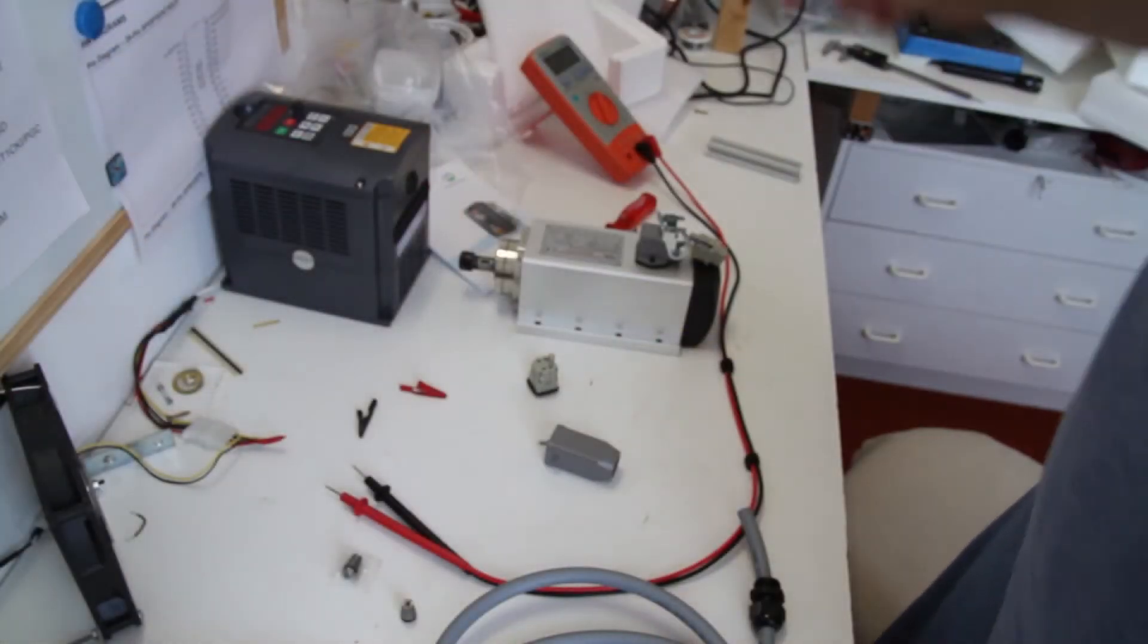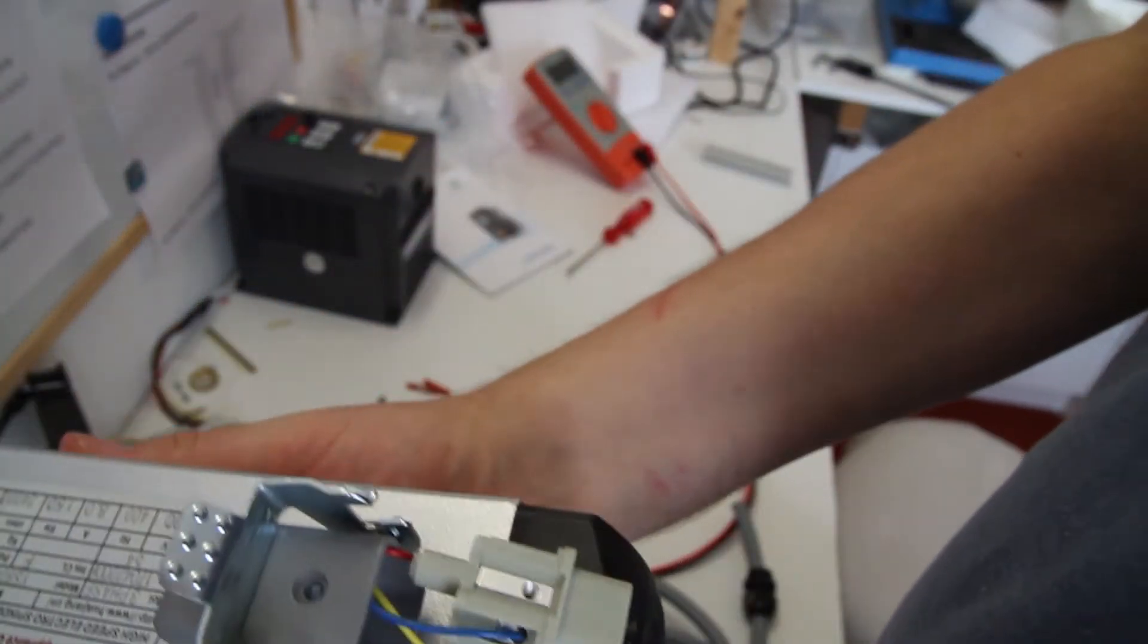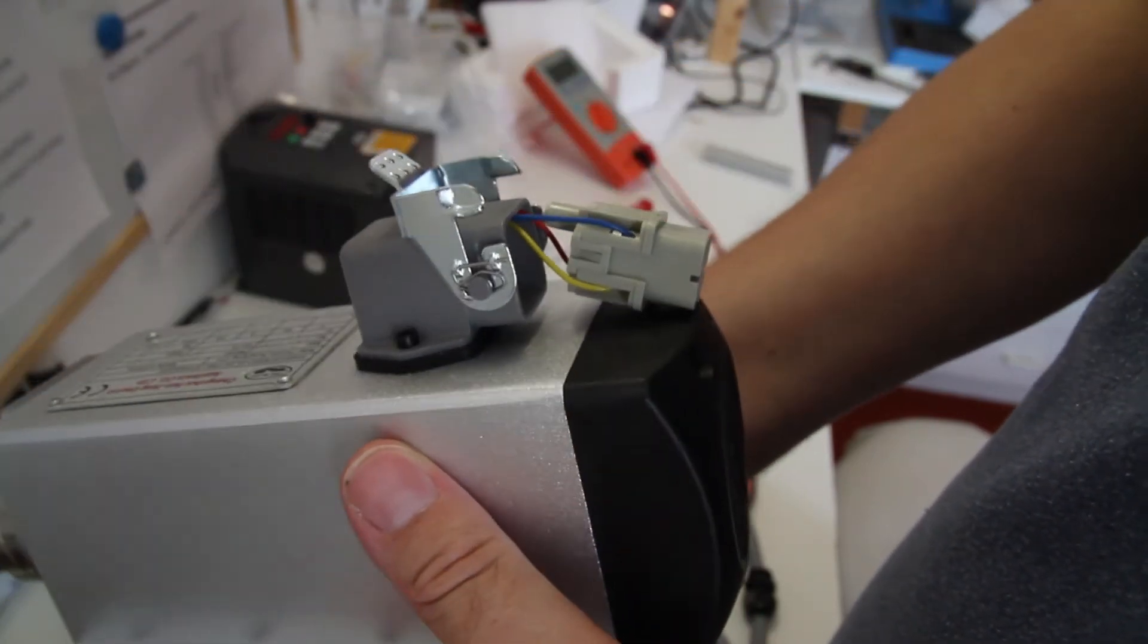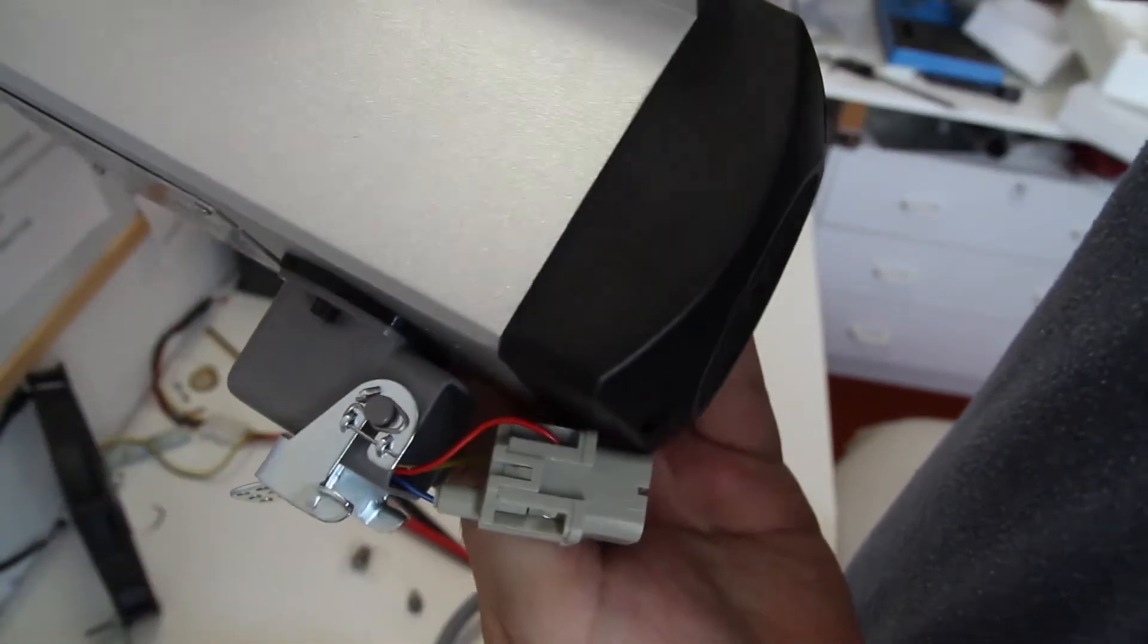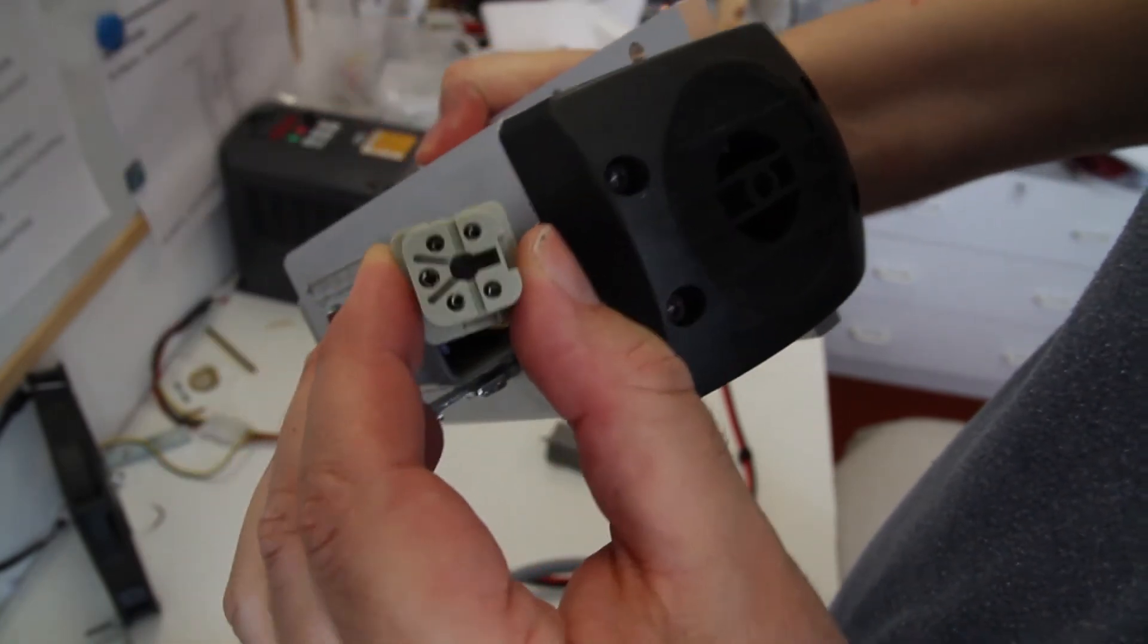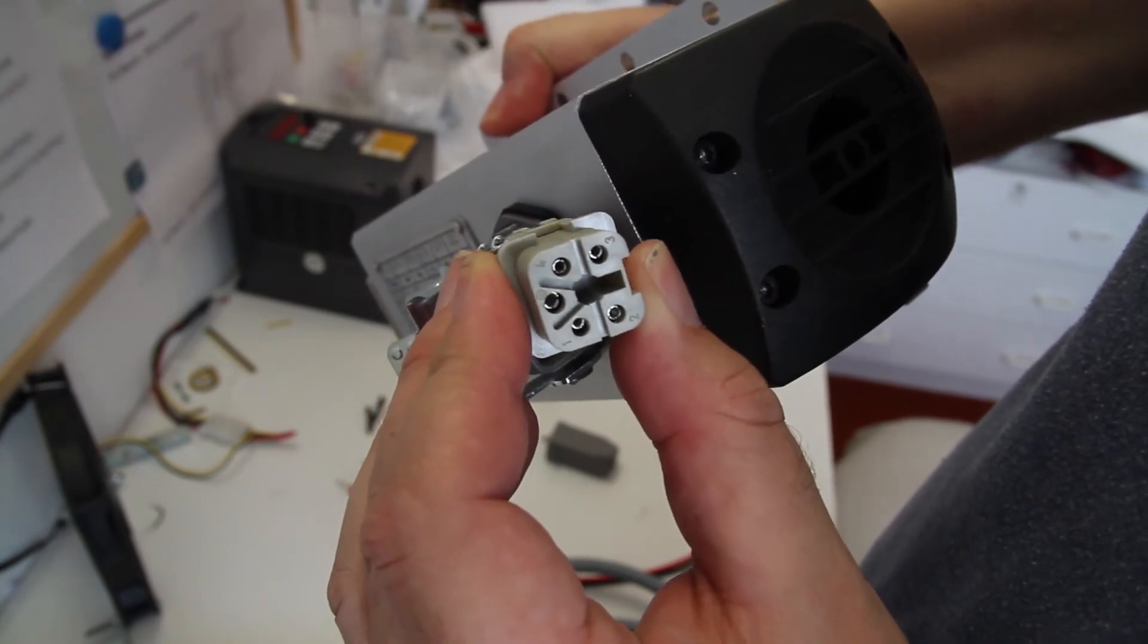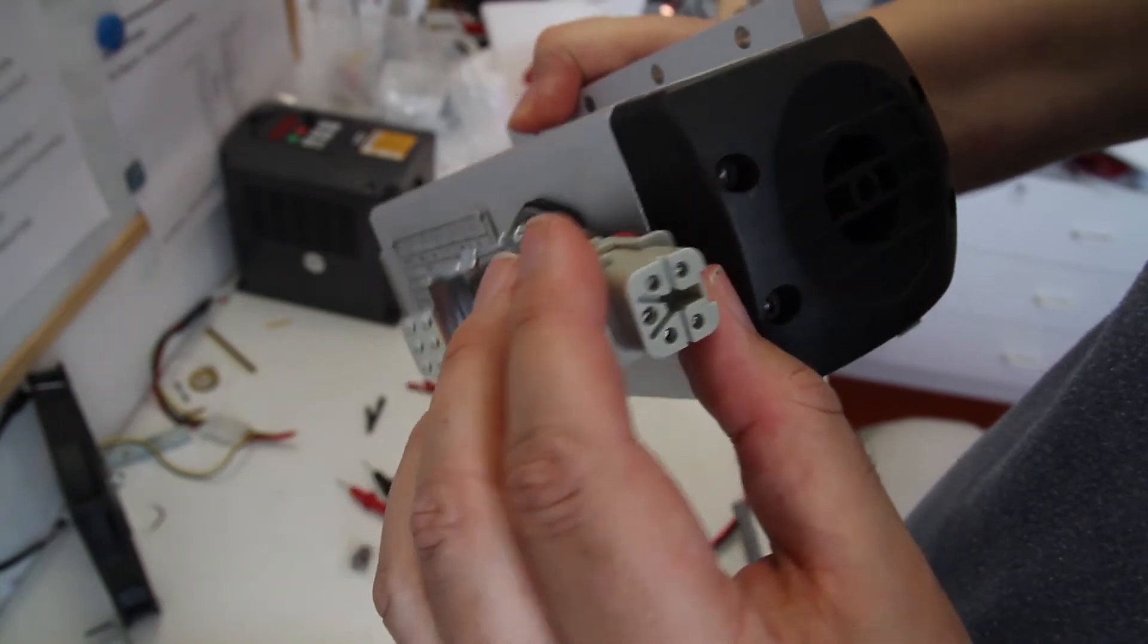I opened up the connector to see how it's wired. The connector is fixed by a screw that should be connected to the ground, and in fact it does, but the IP54 shielding appears to block the connection, or the coating on the housing of the connector has some paint on it that prevents connection with the ground.